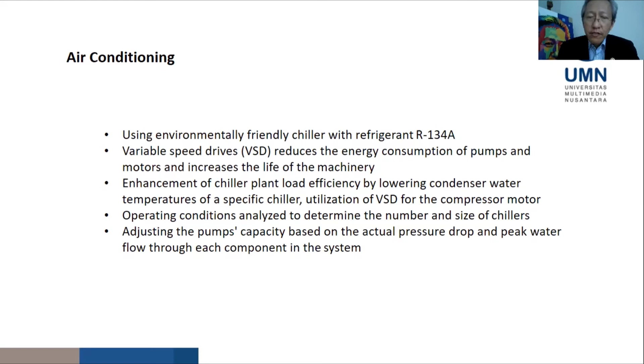We also enhanced our chiller plant load efficiency by lowering the condenser water temperature of the specific chiller, utilizing variable speed drives for the compressor motor, and analyzing the operating condition to determine the number and size of the chillers.